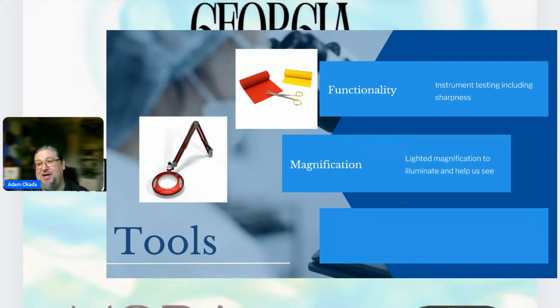Magnification in the prep area. A lot of people don't realize that in prep and in decontamination, robotic instruments require 4 times magnification. That's how you inspect it. There is no insulation test in the IFUs for the XI robotics. And so what they did instead is they said you have to use 4x magnification. Well, in sterile processing, we typically have these swing arm type magnifiers that are on the workstations. Most of those swing arm magnifiers are 2 to 2.25 times magnification. So they're not meeting that requirement. And remember, it's in decontam too. So if you have a swing arm magnifier in decontam, usually that's not going to be 4x magnification there as well. But we need that better magnification.